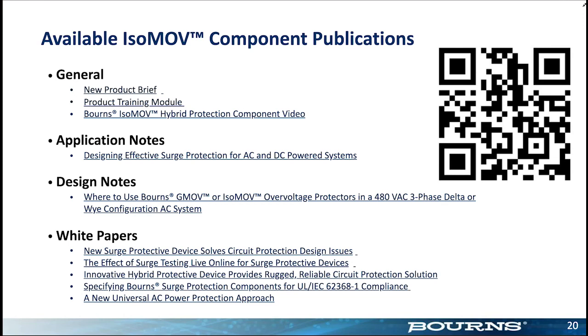Another question that just came in was, how does the breakdown voltage change with temperature? Because in this particular design, the IsoMOV, you have the MOV and the GDT kind of isolated. So if you're working within the operating temperature, which I think on the IsoMOV is up to 125 Celsius, typically you don't have a whole lot of change on the breakdown. They pretty much stay within the tolerance range.